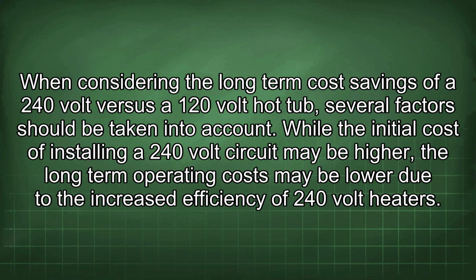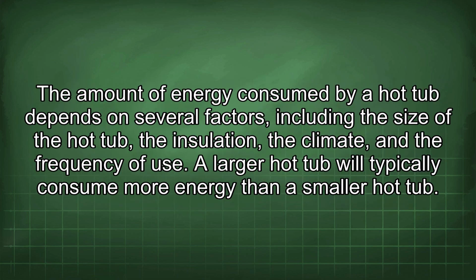When considering the long-term cost savings of a 240 volt versus a 120 volt hot tub, several factors should be taken into account. While the initial cost of installing a 240 volt circuit may be higher, the long-term operating costs may be lower due to the increased efficiency of 240 volt heaters. The amount of energy consumed by a hot tub depends on several factors, including the size of the hot tub, the insulation, the climate, and the frequency of use.